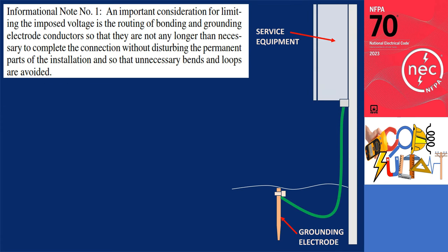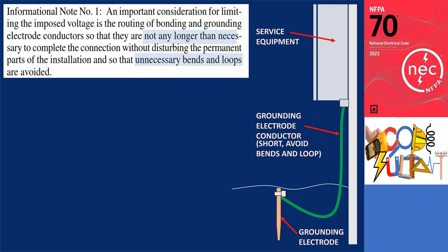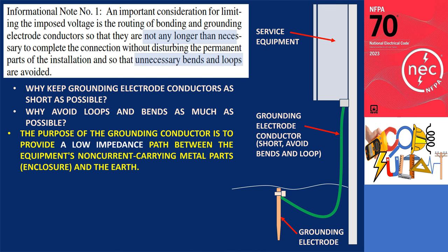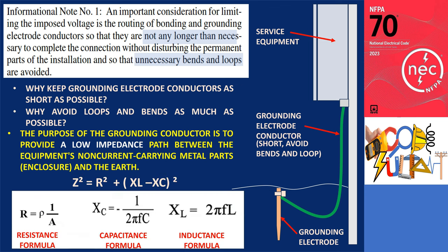Informational Note No. 1 calls attention to the fact that limiting voltage to ground includes keeping grounding electrode conductors as short as possible and avoiding loops and bends as much as possible. The earth grounding conductor aims to establish a low-impedance path between non-current carrying metal components and the earth. The term low impedance encompasses both resistance, which remains constant regardless of signal frequency, and reactance, which varies with frequency.